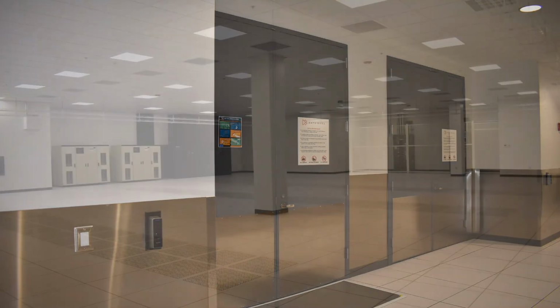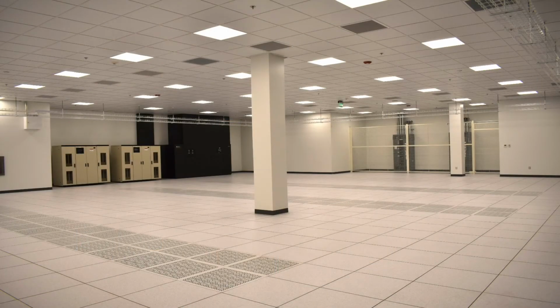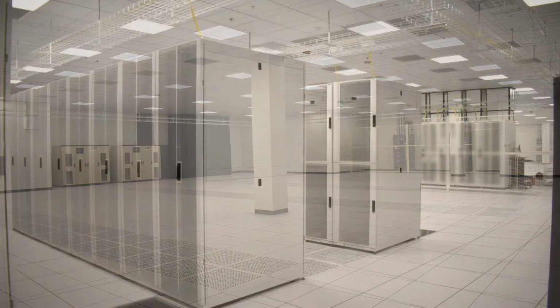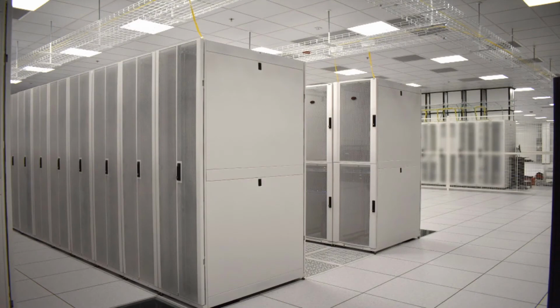Data Hall 1 provides several colocation options. Unmodified, the cabinets will support up to 10 kW of draw utilizing a traditional cold aisle, hot aisle configuration. The cabinets we use in this facility are 52U rack units. They are 24 inches wide and 48 inches deep with a mesh front and back door. The 52U cabinets provide 25% more colocation space in the same footprint as compared to 42U cabinets.